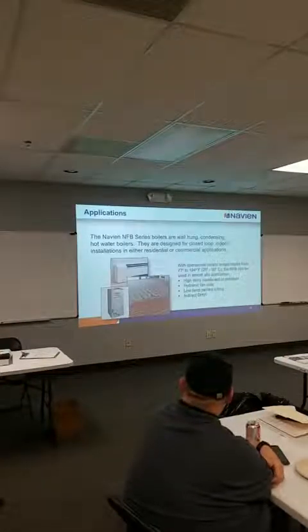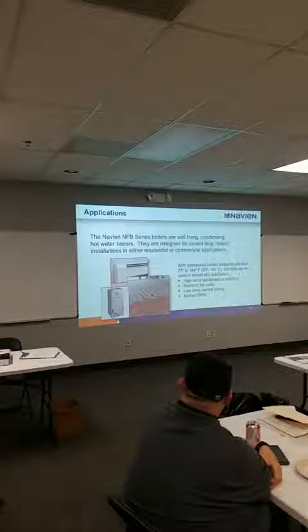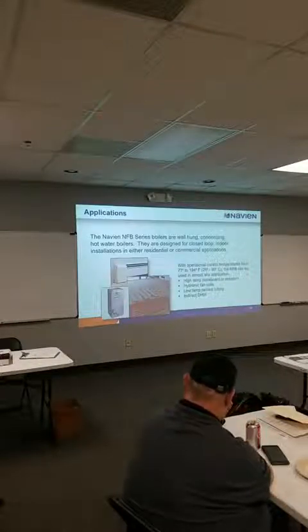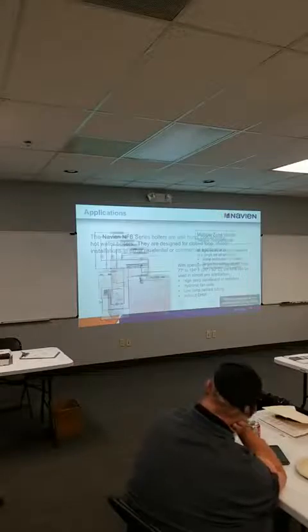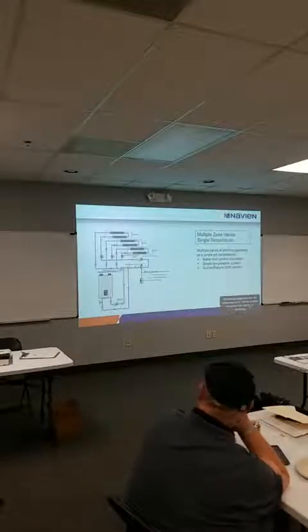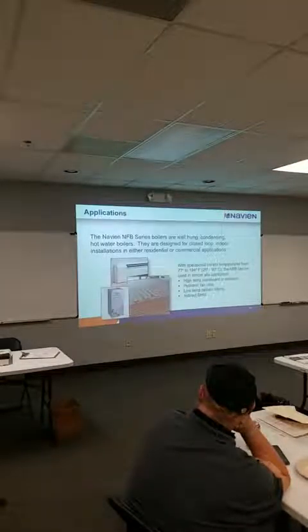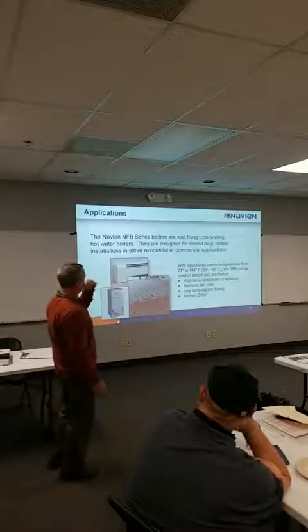Do they use pressure or conductivity? So they use pressure. I think at 6 pounds, it airs out. And at 6 pounds, the combi will try to autofill itself, but the boiler relies on your external autofill valve. And temperature wise, I think, if you're using the outdoor sensor, again, 194 degrees.